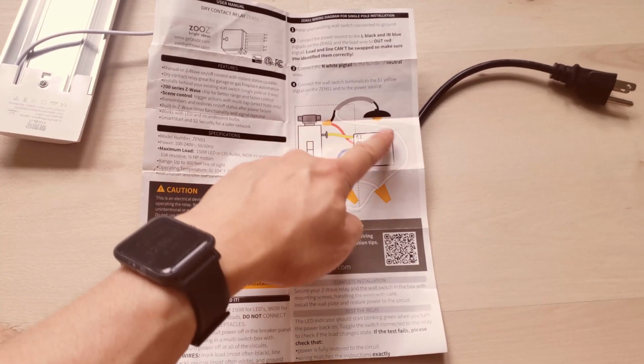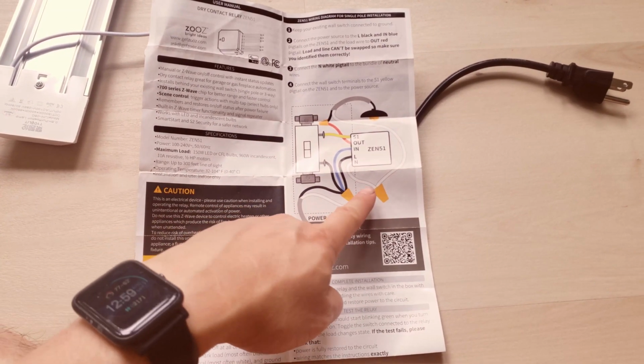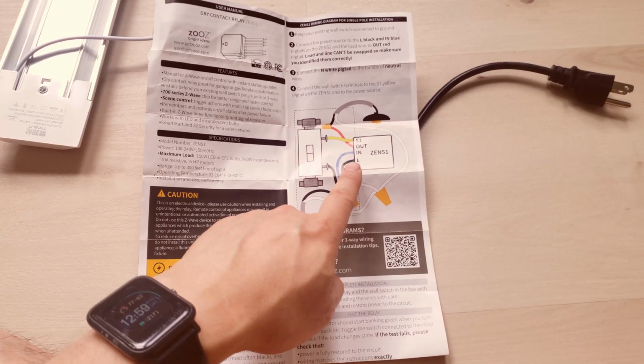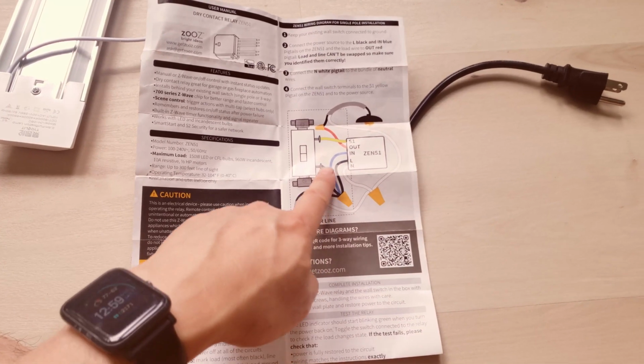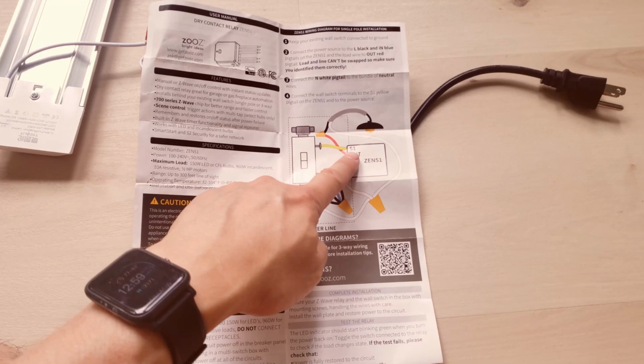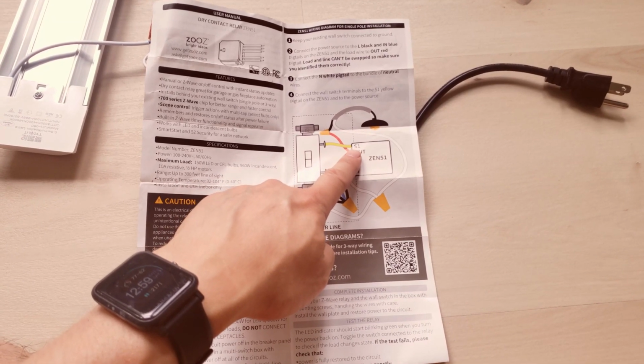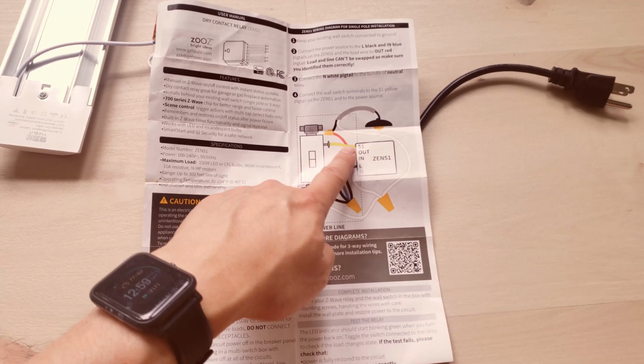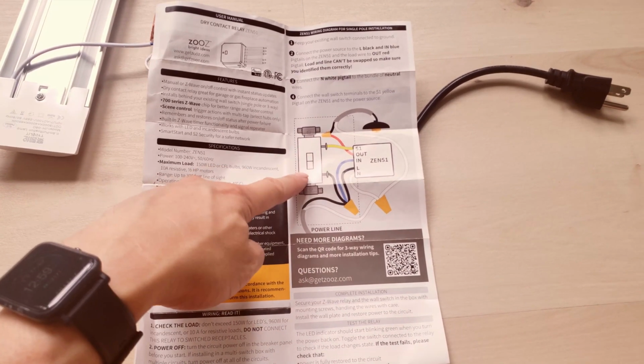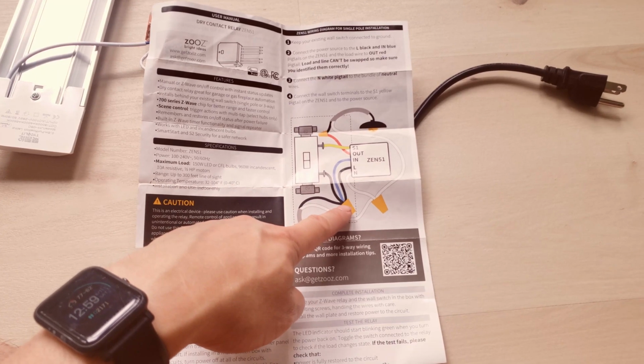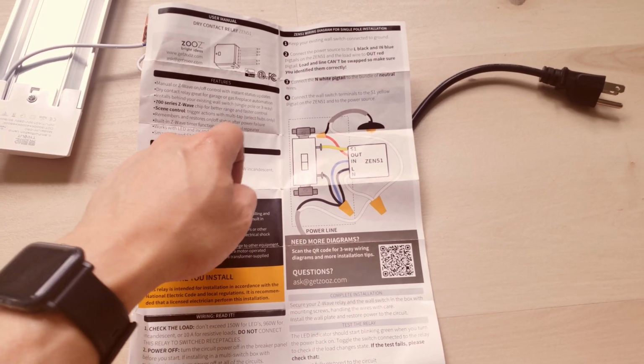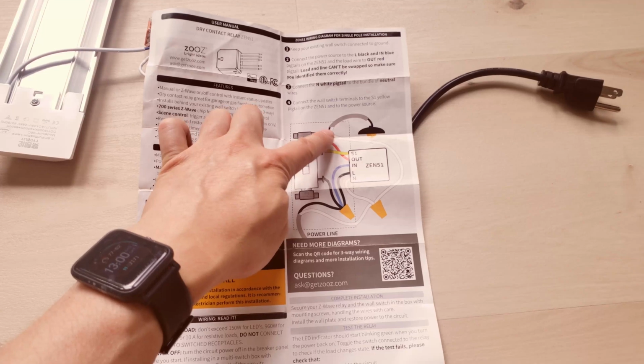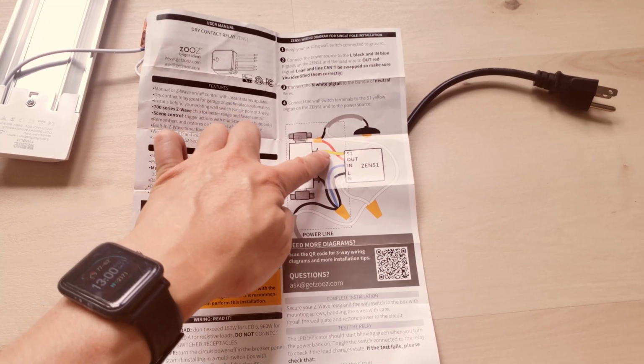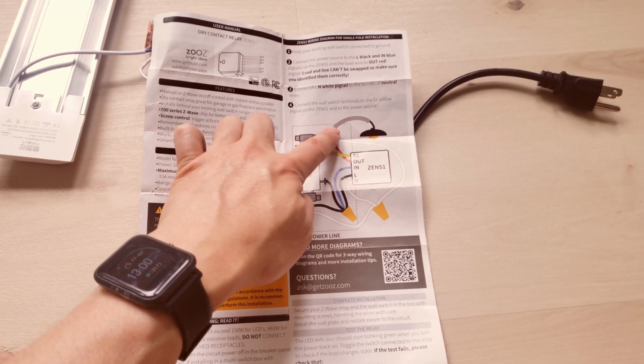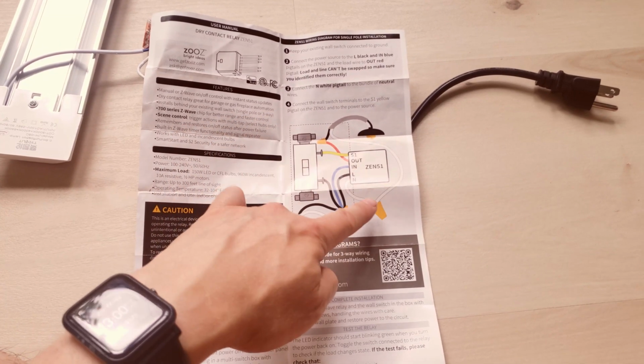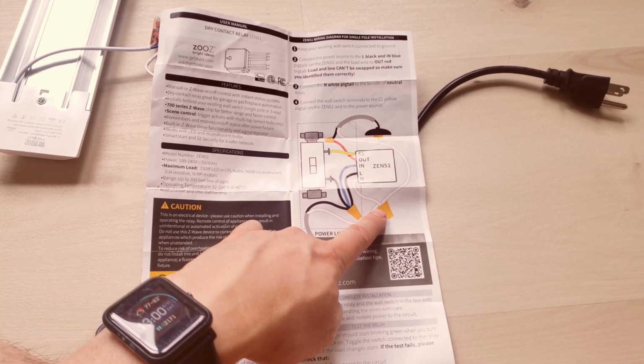All of the neutral go into the neutral. The load, the black lines go into all the black lines, including the blue. Your S1, which is the signal or the switch, goes into the switch. The other end of the switch goes into the black. Your lights only have two wires coming out. The black goes in with the out, the red, and the white of the lamp goes into the white, which is all the other neutrals.